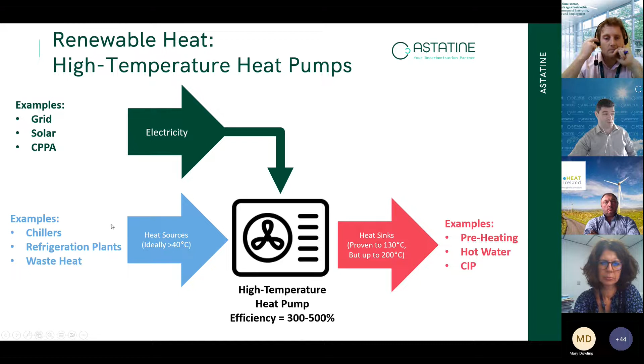And for us then, the task is designing a heat pump, which I would say is a much more tricky task than a boiler. A boiler is a much more generic piece of technology. A heat pump needs a lot more engineering and design work, which means it requires a lot more knowledge and expertise, which is maybe one of the reasons it has been slow to come to Ireland until recently. But it does certainly need a degree of engineering expertise to design a bespoke system for that site. And once you do that, then you can see how to get the maximum efficiency depending on what sources and sinks you have on that particular site.